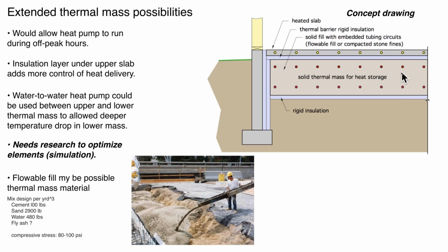In some projects, the engineers will specify flowable fill. It's actually material that an excavator can dig out. It runs between 80 and 100 pounds per square inch compressive stress. It is strong enough to support the slab above it without any problems. Because there is cement mixed in with the sand, you have better thermal properties. I'm currently looking into this, trying to get good solid information on these materials so we could do some types of simulations, but I wanted to show the concept to you. Again, this is trying to move away from very expensive multiple 1,000-gallon tanks of water into something much less expensive and logistically easier to incorporate into a project.